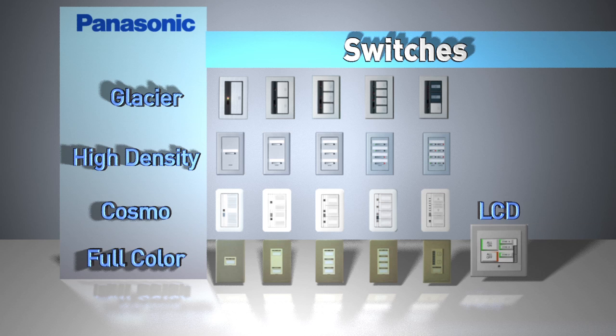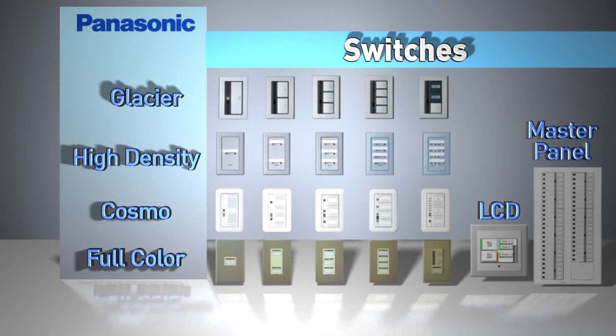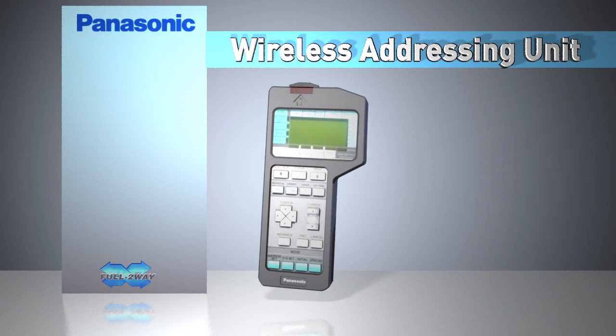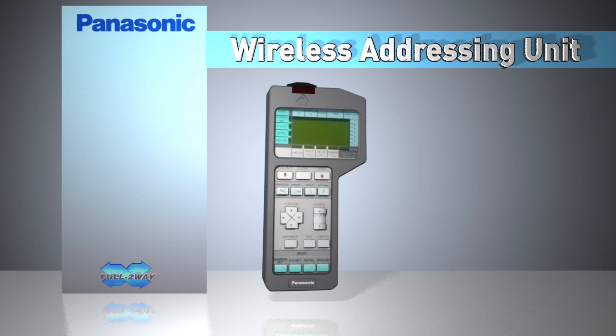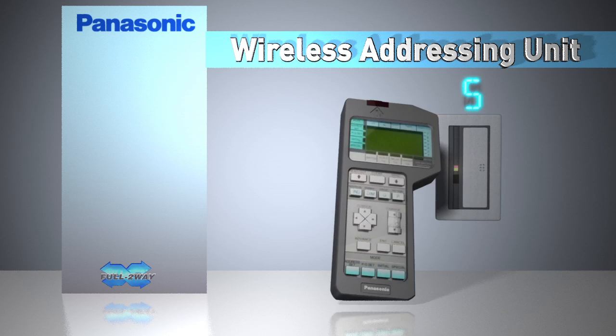Full two-way also includes a 24-button LCD touchscreen switch that fits a two-gang box and displays three custom screens. The master switch provides additional monitoring and control of an entire building or campus from a central location. The wireless addressing unit is used to read a switch address and then create duplicate switches or change a switch address to optimize lighting in newly allocated spaces.